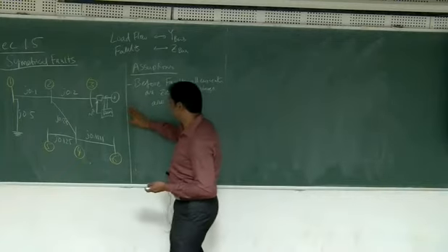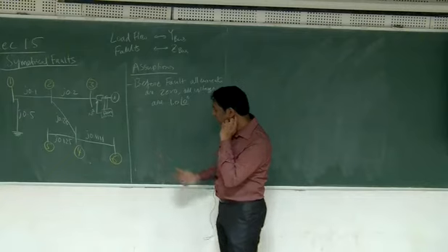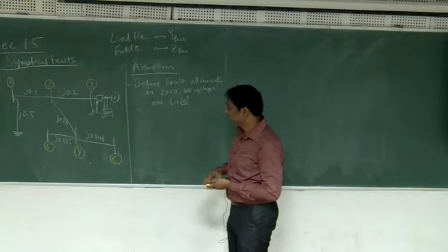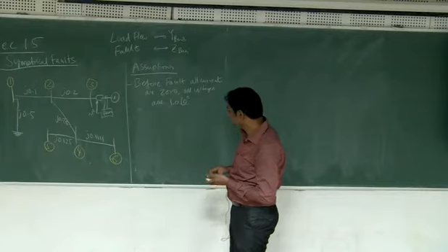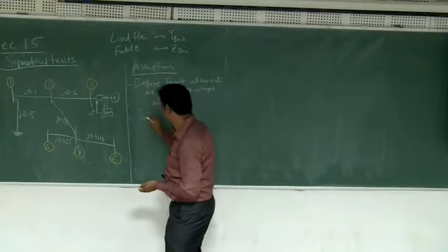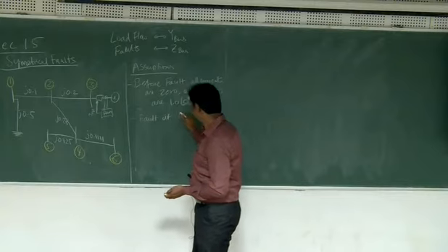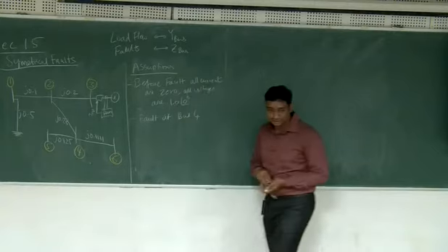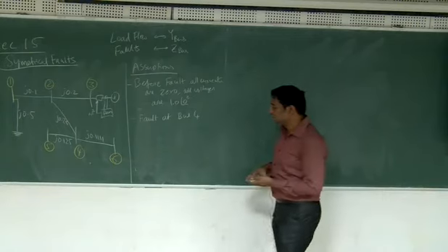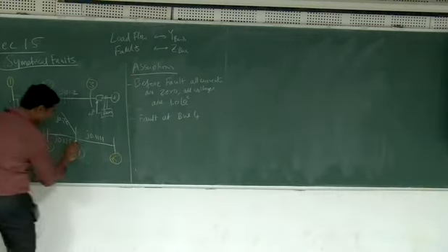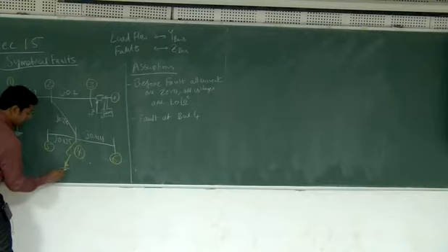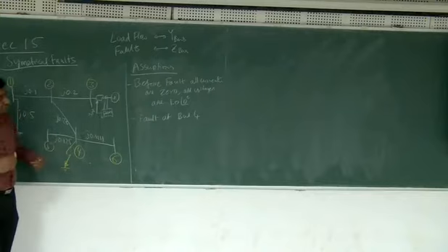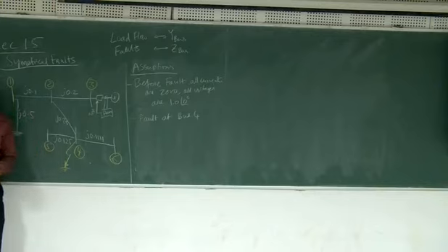Under this situation, let's choose where do you want to get the fault? 4. Okay, so fault at bus 4. Now usually the fault is represented like this, so some kind of arrow. Now the fault will have some fault impedance also, but right now we are assuming that the fault impedance is 0. That means the impedance between this point and the ground, we are assuming 0. Okay.